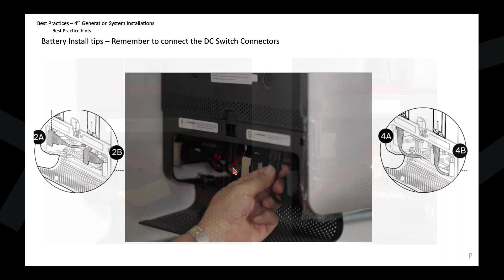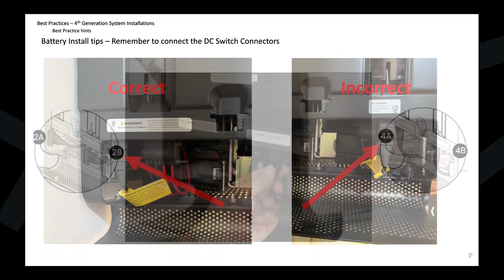There's a right and wrong way to install those connectors. When you put them into the DC disconnect switch, there are two ways it can go, but only one correct way. On the left-hand side is the correct example, and there's a little latch. As you slide that connector into the slot, it'll click in and lock. Give it a good tug test to make sure it's secure.